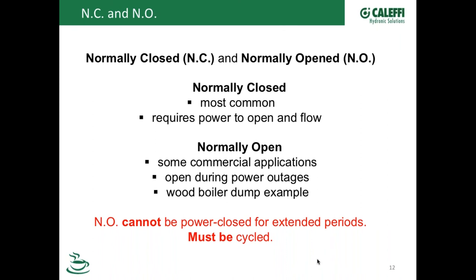Now where that valve can be handy, where it gets applied a lot, is maybe on a dormitory or something like that. And the reason they would do that is that if there's a power outage, the valve is going to go open so they can get some gravity flow through that, and it might prevent a building from freezing up or keep the room to a certain temperature even though the power's out in it. Now obviously you might not have a pump running, but it might be enough to keep the building from freezing up or something like that. So I don't see a lot of those normally open valves being applied in residential applications, but I'm gonna ask Cody to step in here a little bit and tell me a little bit about some of the things to be aware of when you use a normally open valve. So tell us some more about this, Cody.